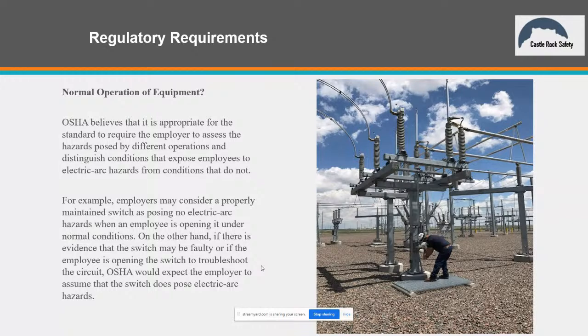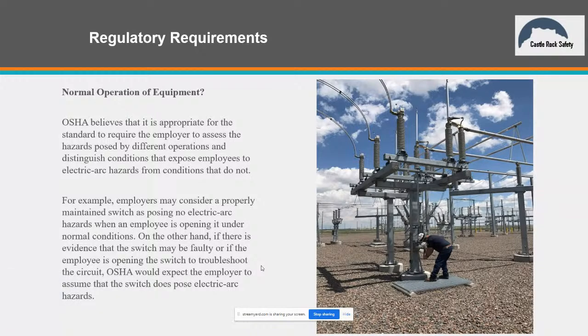Obviously, the easiest way to work your way through that is you don't put anybody in merely flame resistant clothing, because flame resistant isn't arc resistant, but arc resistant is flame resistant. So that's one of the things about this standard that's a little confusing. They'll say under certain circumstances, yeah, you're going to be outside that 2-calorie boundary, you don't need arc flash clothing, but you do need flame resistant clothing.